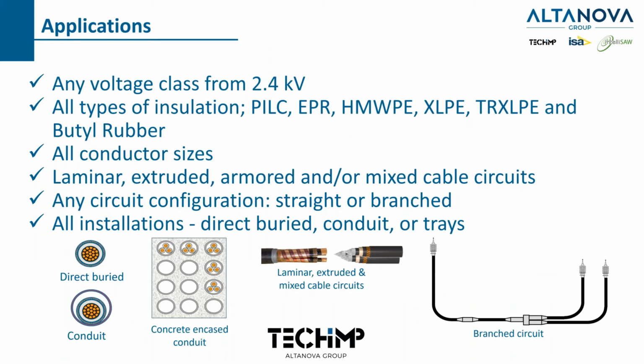So the question is, what voltage is applicable for partial discharge testing? The answer is anything at 2.4 kilovolts or above. Below that, we really don't get partial discharge, or we can't measure it if it does exist. What types of insulation? Pretty much anything you have: paper insulated lead, EPR, and the different variations of cross-linked polyethylene, whether it's tree retardant or high molecular weight. Pretty much anything you have, we can do, in any configuration as well.